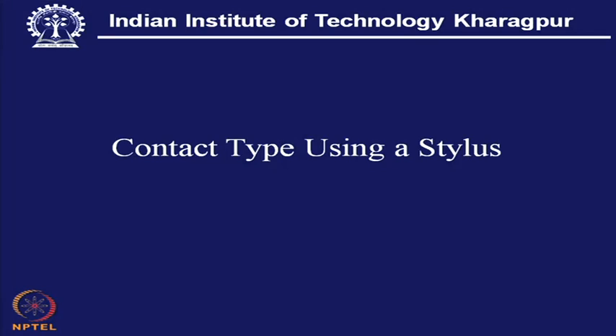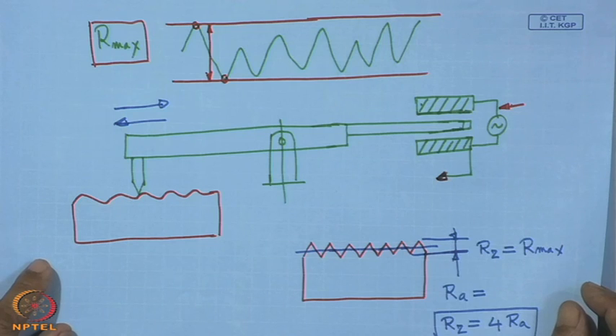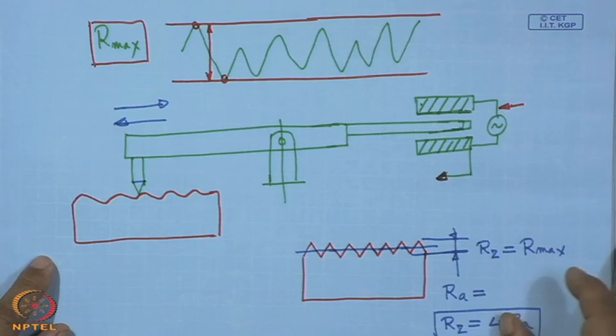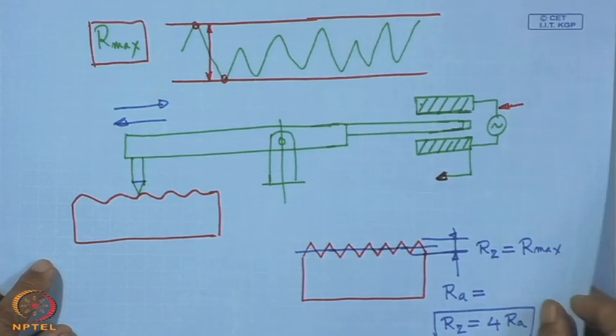Number two, when the surface is not so hard, even with a small load from the diamond stylus, fine scratches can be clearly visible on the coated surface or any surface of interest. So one has to look into this aspect of micro scratching by the diamond stylus. If somebody makes several runs of surface measurement, one would expect many scratch lines on the surface. This is limitation number two.